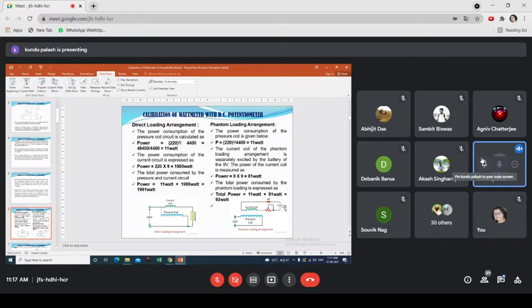That's why there is a need to perform the calibration circuit using two potential sources, one a high voltage source and another a low voltage source of about 6 to 9 volt. In this circuit only the power dissipated by the current coil and the pressure coil is supplied. There is no physical power consumed by the load, so the load is not present here. But the wattmeter can still be operated under different loading conditions. That is the advantage, because the power requirement of the two supply sources will be much, much smaller. The calculation shows this.